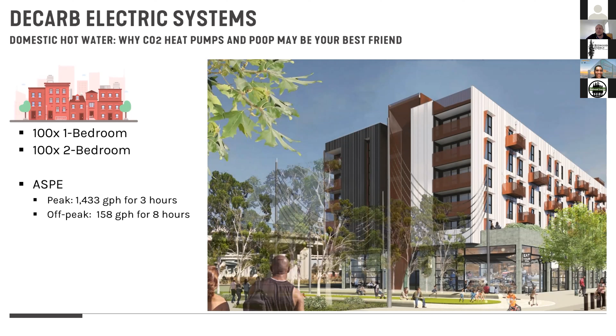So just as an example, we have a project that we're working on here locally using actually the exact same technology that we're looking at in another climate zone. So I'm just using it as an example of a 200 unit apartment building. When we start to look at which systems pair with which use profiles, I hear a lot when I'm on calls in California that they're like, oh, heat pumps, it has a COP of 3, it's great, saves the day. And yes, a heat pump can have a COP of 3, but oftentimes they don't. And especially when we look at air source heat pumps, that COP is highly variable, and it tends to drop off at the exact same time that we want it the most to be high.